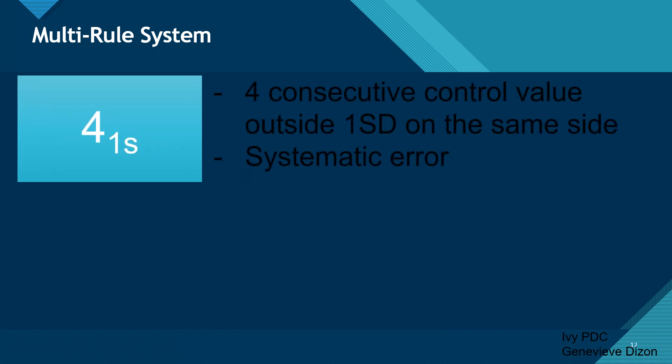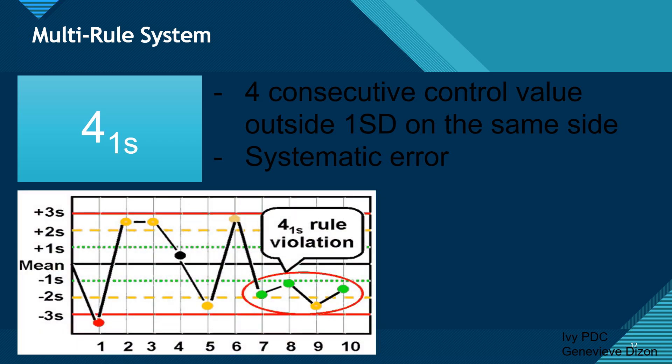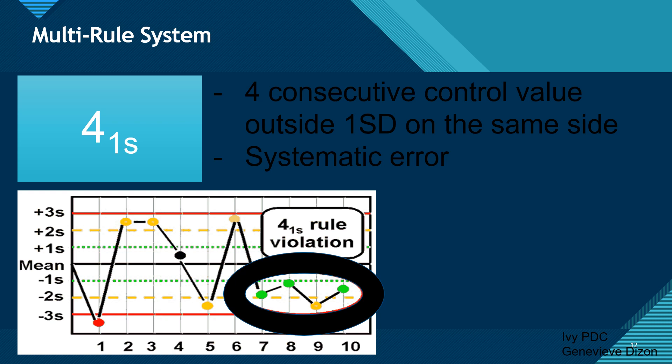The fifth rule is the 4-1-S rule. These are four consecutive control values located outside 1-SD, and they should all be on the same side. This is a form of systematic error. There should be a minimum of four consecutive control values, all under 1-SD, either on the positive side or the negative side. With this systematic error, we also reject.